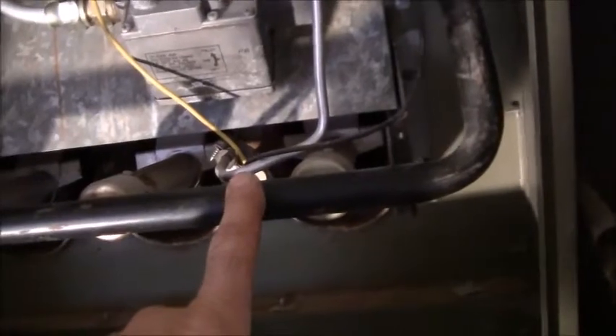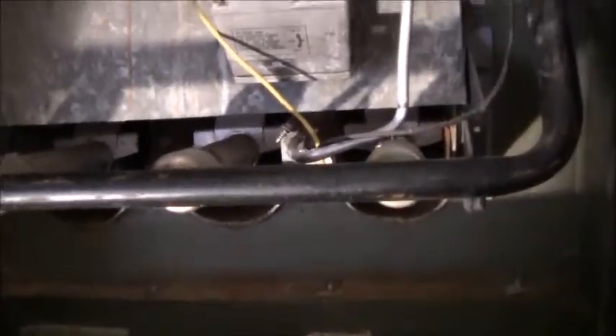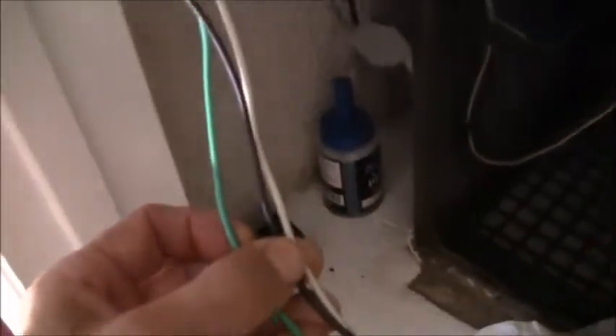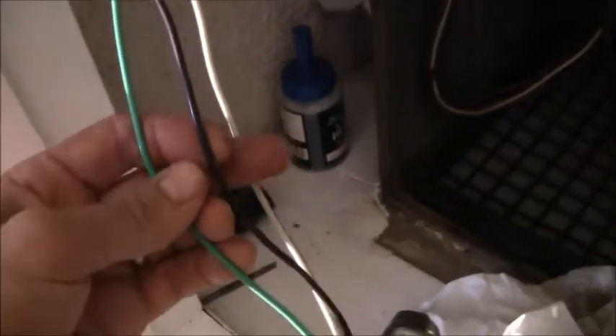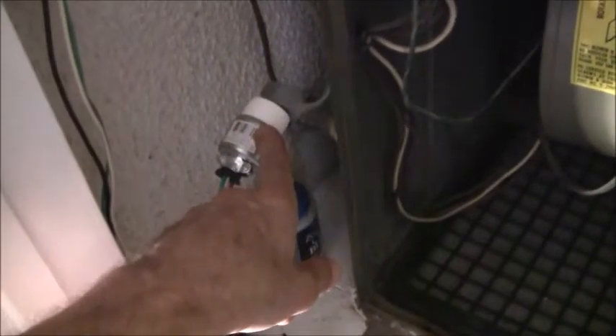All right, right now I want to see if I can get the thermocouple to light off. So what I did was I built this small little extension cord where the conductors are exposed, so I can put my amp probe on here real easily. On the furnace electrical, I'm going to plug it in here so I can get my amp draw with the doors on with no issue. So I'm going to go ahead and plug this in. Okay, so we're plugged in here.